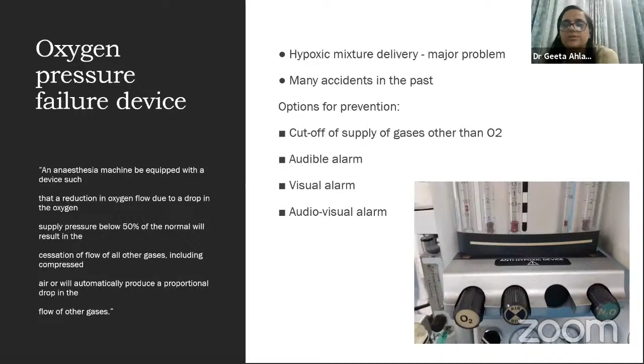We should be able to cut off the supply of gases other than oxygen. We should have alarm systems, whether audible, visual, or audiovisual alarms. Our standard guidelines mention that any anesthesia machine should be equipped with a device which would immediately detect the pressure fall of oxygen. And if the oxygen pressure goes below 50, it should be able to cut off all other gases, including medical air. So with this in mind, we must have our oxygen pressure failure devices absolutely right.